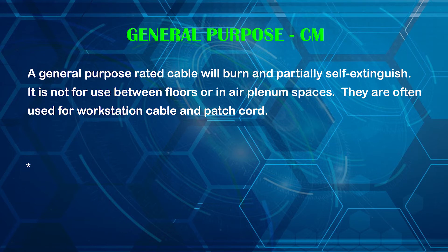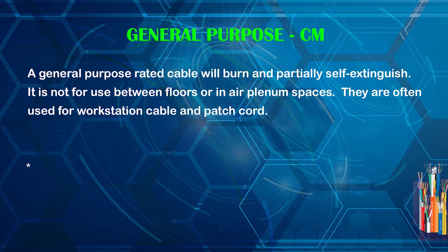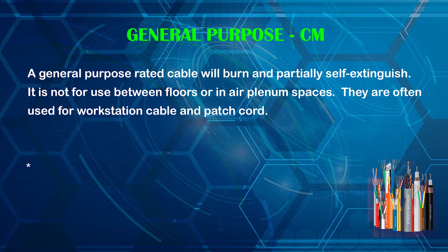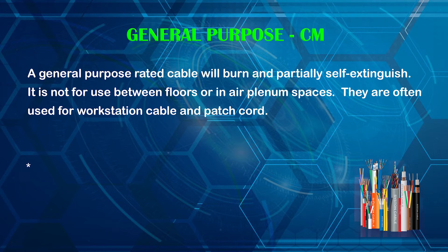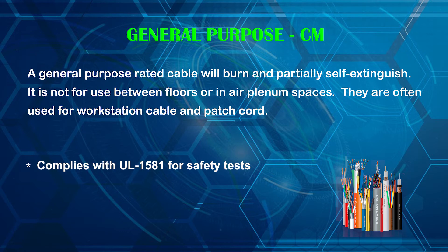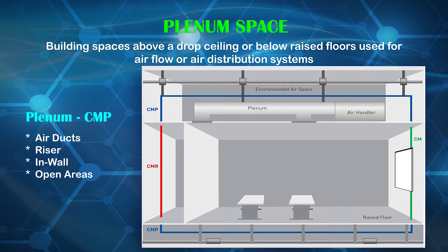A general purpose rated cable will burn and partially self-extinguish. It is not for use between floors or in air plenum spaces. They are often used for workstation cable and patch cords. General purpose rated cable should comply with UL 1581 for safety testing of electrical wires, cables, and flexible cords.